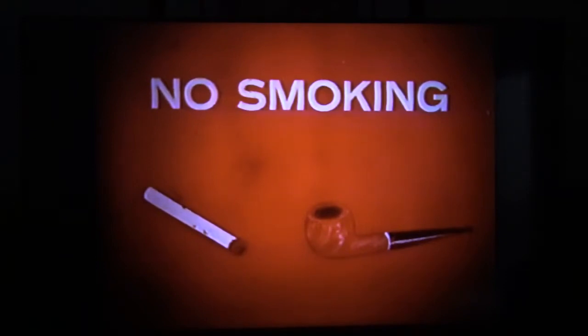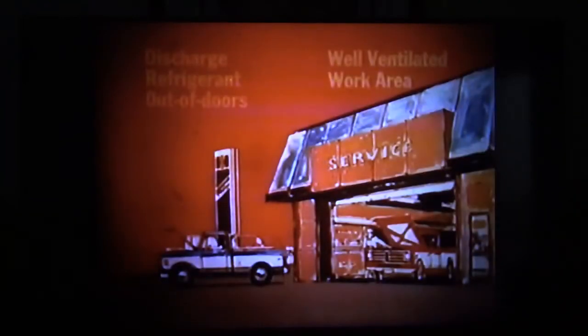Refrigerant 12 is not combustible, but when exposed to flame, it changes to a highly poisonous and deadly phosgene gas. Because liquid refrigerant evaporates so rapidly, the resulting gas may displace the oxygen in a small enclosed area. Therefore, always discharge the refrigerant out of doors and use a well-ventilated area when servicing the refrigeration system.